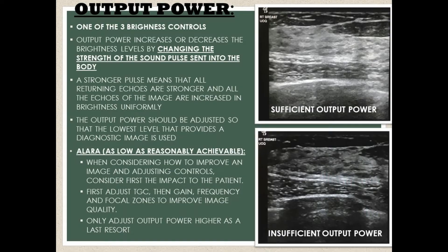The output power control is one of the three brightness controls on an ultrasound machine, and it increases or decreases the brightness level of the entire image by changing the strength of the sound pulse that's sent into the body. A stronger pulse means that all returning echoes are stronger, and all the echoes of the image are increased in brightness uniformly.